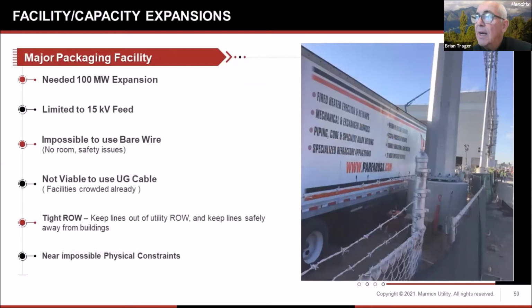Let's take a quick look at a project that was done in the last year or so. This is a major packaging facility, one of the largest packaging facilities in the world. They needed a 100 megawatt expansion and didn't have room. They basically had room for one building. They were limited to a 15 kV feed. It would have been better to bring it in at 35 or 69 kV, but they were limited to 15 kV. It was impossible to use bare wire. There was no room. There were safety issues. It was not really viable to use underground cable. The facilities were already massively crowded.